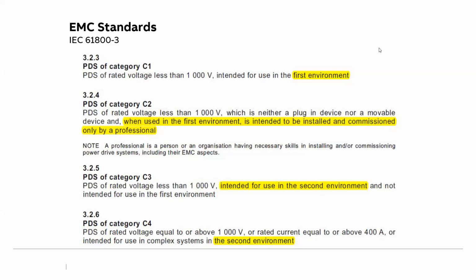Now, most of our applications, if it's a commercial or residential building, mostly fall under the first environment. So within the first environment, C1 or C2. For that, we need to understand that it depends on the end use application. Now, this is generic. This is not about VFD. We are talking about any electronic equipment. So the C1 category is any product which is a plug and play device, which does not need professionally trained manpower to install, commission, and use, and which is a movable product. For such products, the C1 category is recommended. So all our plug and play devices like laptop chargers, connectors, mobile chargers fall under the C1 category. Then the C2 category is any device which is not a movable product, which is immovable and intended to be installed, commissioned, and used by a trained person, and which is not a plug and play device. All such devices fall under the C2 category.